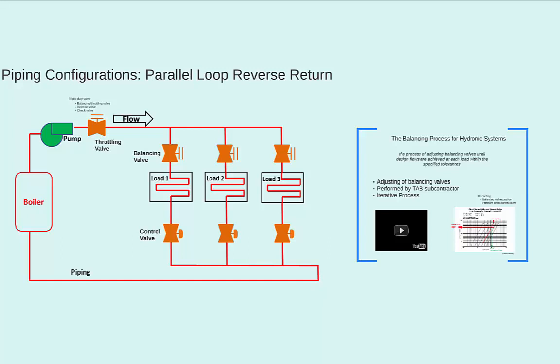If the system was not balanced correctly and excessive amounts of water want to flow through a particular coil, one or maybe two things will happen. First, the control valve is going to try to compensate by always being partially closed. This reduces its operating range and thus its ability to control the amount of flow being provided to that coil. Second, if the system was extremely unbalanced, overheating may occur in the space served by the coil when the control valve is barely cracked open. To tie that back to some control theory we have already discussed, we would say that particular coil and control valve assembly would have excessive system gain.